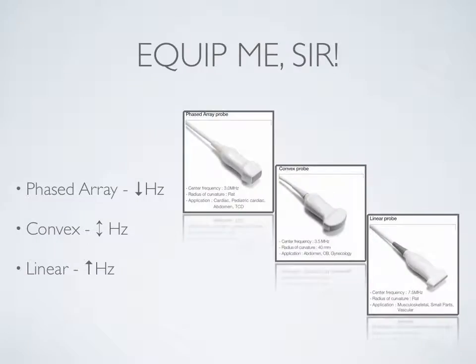And that comes down to probe selection. So these are the 3 standard probes that you're going to see on most portable ultrasound machines. You have the phased array, the convex, and the linear. When performing a FAST exam, typically you'll find either the phased or the convex probes are used. A more skilled technician or a very skilled physician will end up using the phased array probe because it has a smaller footprint and allows you to wedge between ribs to eliminate rib shadows and get a clearer view. The convex probe has a nice wide footprint, so it's really easy to learn with, and it gives you very deep views because of the way the crystals are aligned in the probe itself. The linear probe is what we typically see for procedural things and will be discussed a bit later.